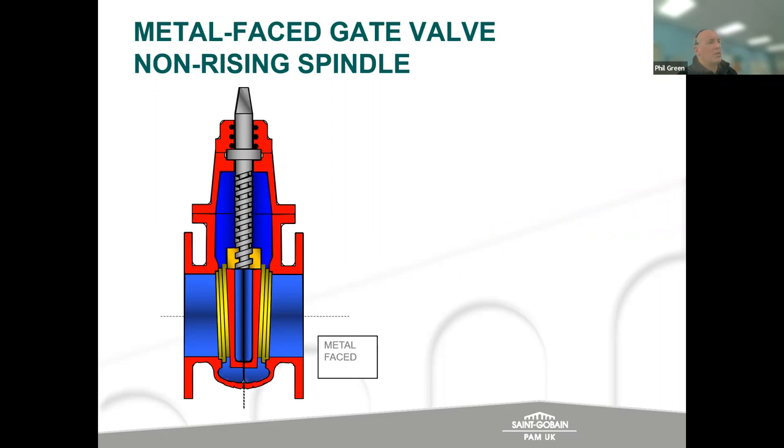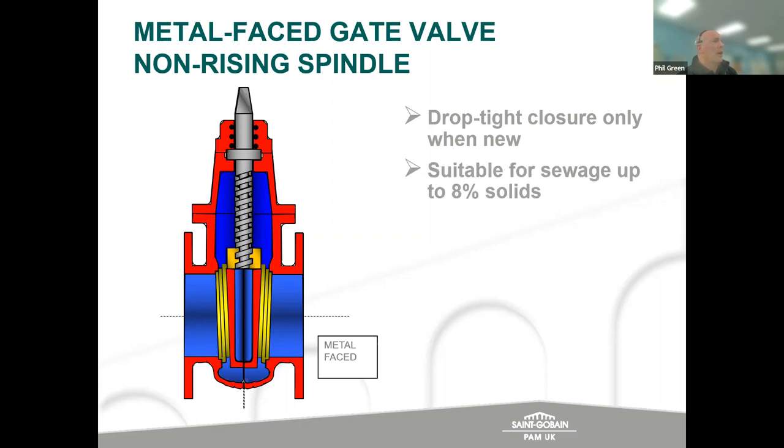Very similar to the resilient seated, but these are generally recommended to be used with raw water and sewage because of the metal gate. They've got the ability to deal with any, let's call it, contaminants that might lodge in sewage systems and sit in the waterway and on the seats.